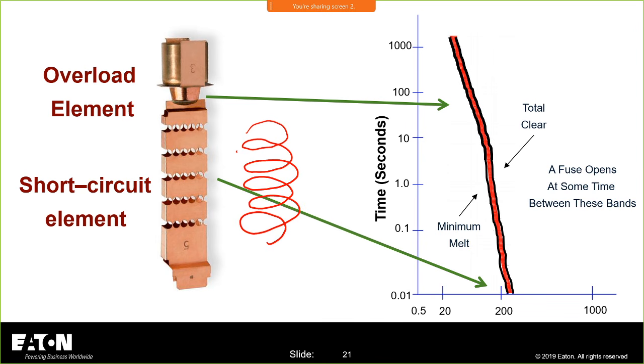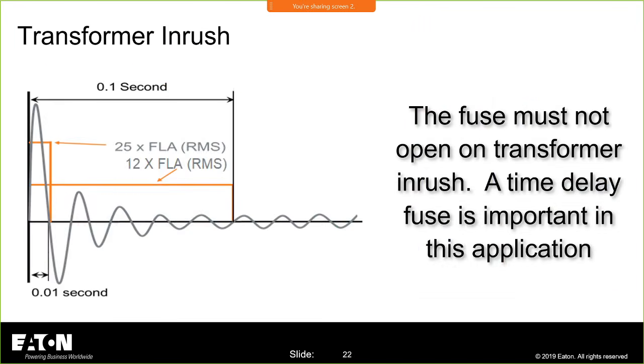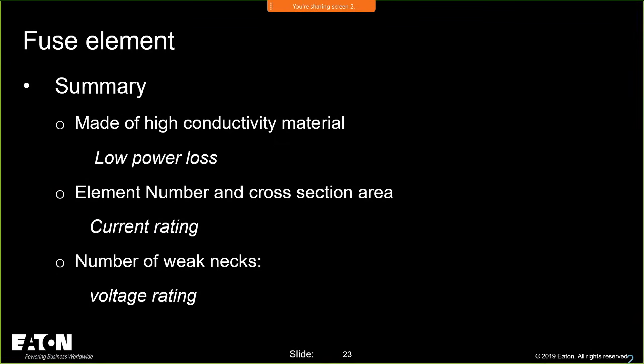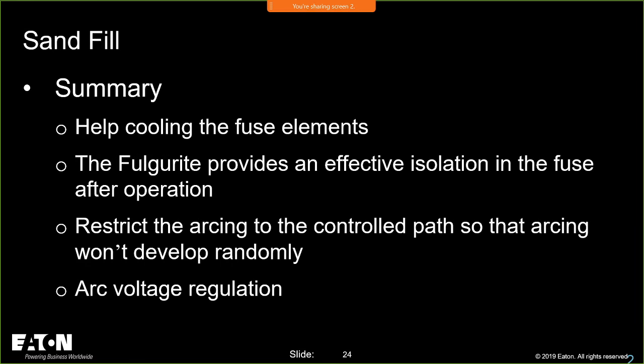It's not a straight element like this. So if you ever opened up a fuse or saw a cutaway of a medium voltage fuse, the reason you see that coil is because the number of those weak necks gives me my voltage rating, and I need to coil that inside the medium voltage fuse tube. So the sand fill that's inside has a lot of functions and features. The sand in there helps cool the fuse elements, and whenever I open that fuse, when I put a lot of current through there, I'll create fulgurite that will basically insulate and isolate the circuit once that fulgurite forms.